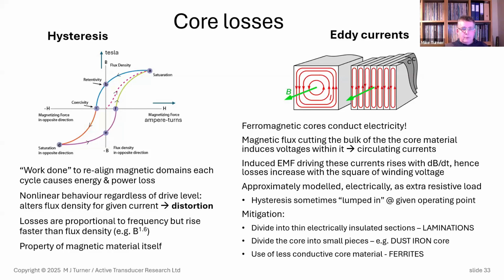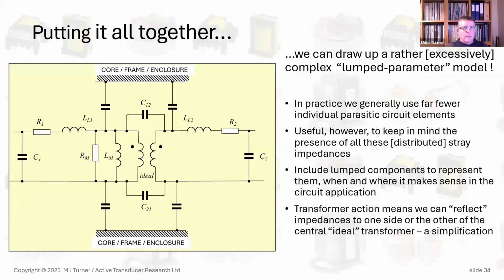Eddy current loss is probably more of an issue in audio transformers. We've got a core that conducts electricity as well as magnetism very well. We get circulating currents within that material because of the field in there, and that causes power losses. And we can show that as a shunt resistance across the winding here.